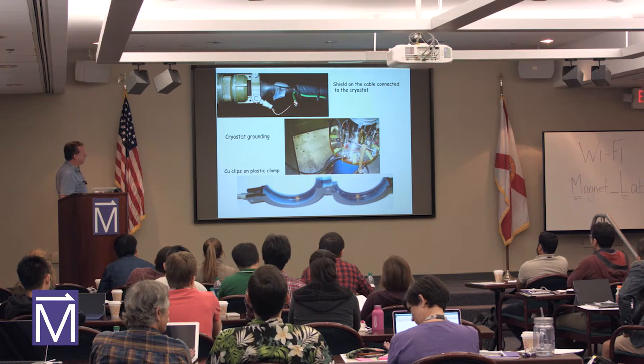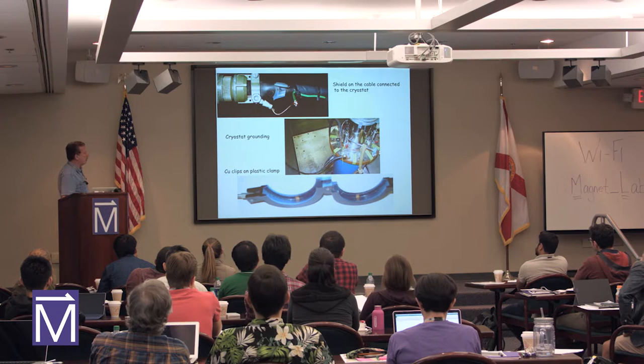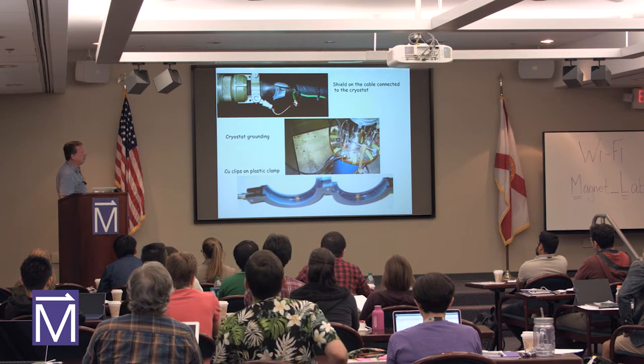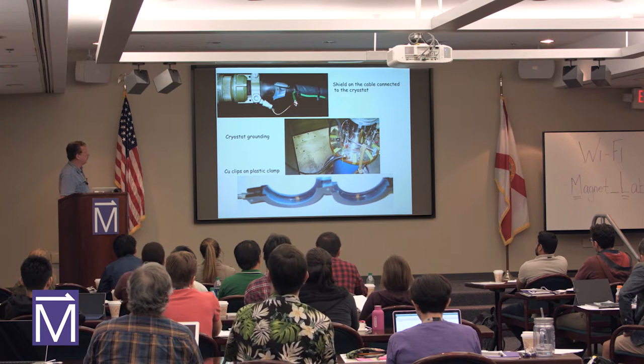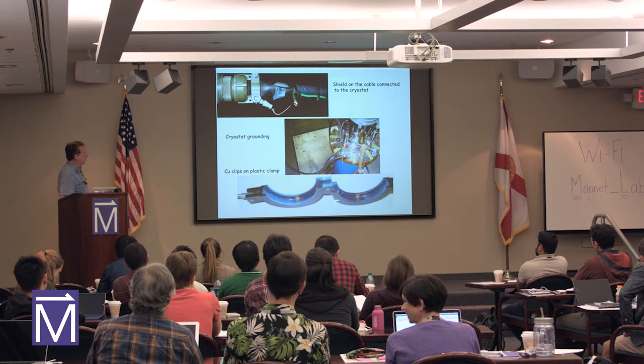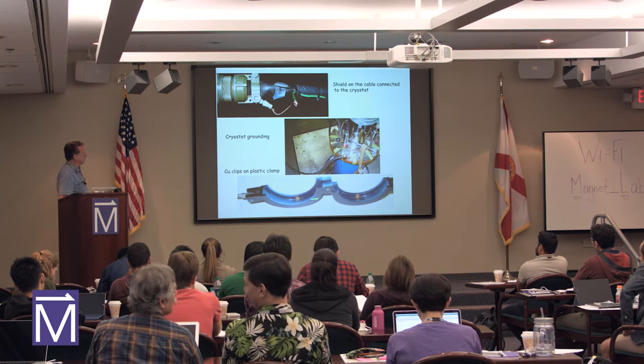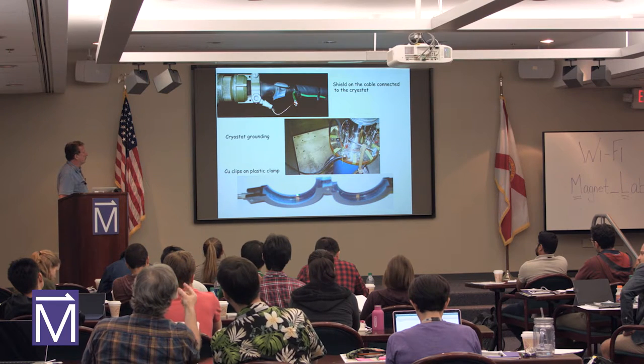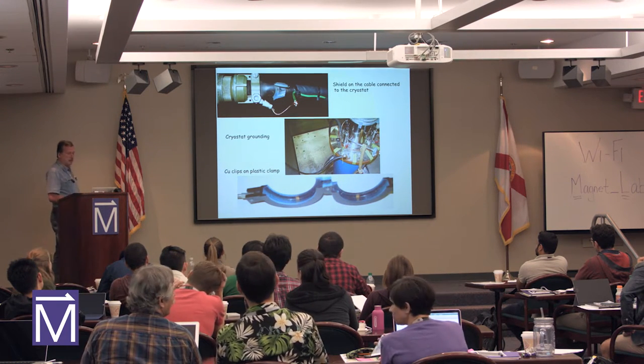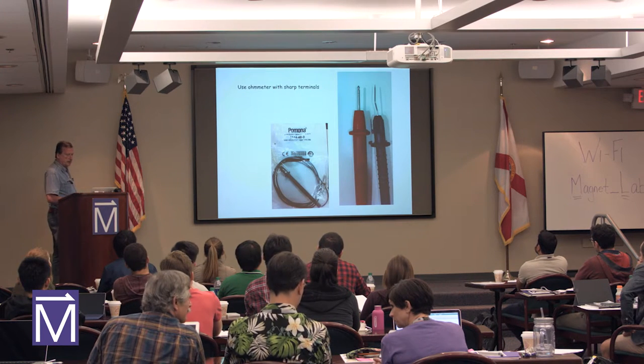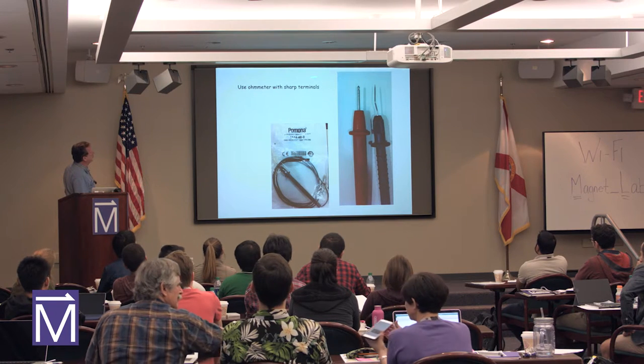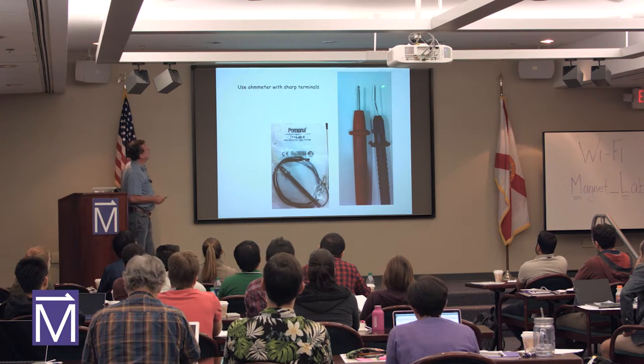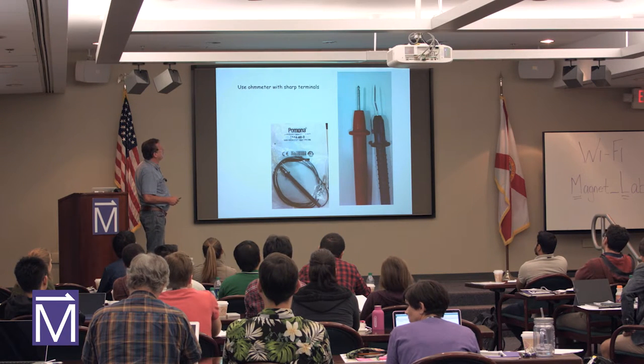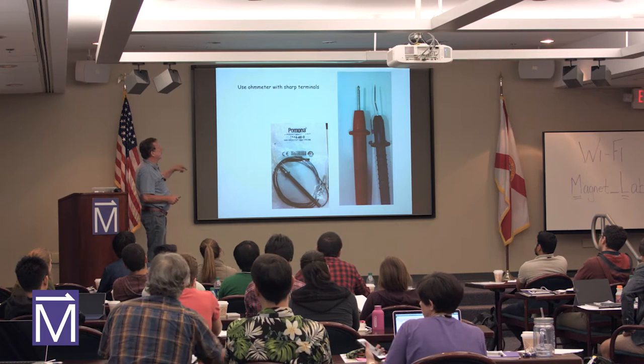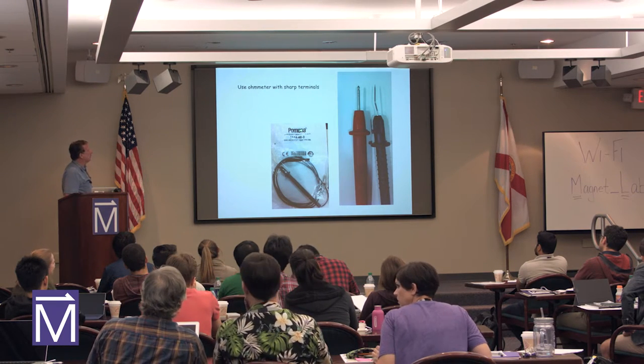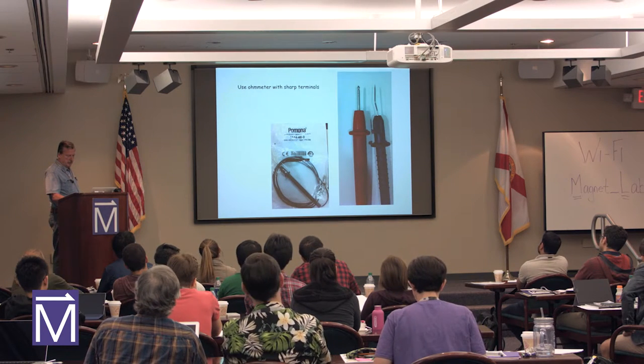Those are typical plastic clamps. You can isolate pumping lines, but remember they are made not to isolate ground, they are made to be cheap. And in industrial application, because of that, they have those small copper or brass clips which must be removed. This is an example of very sharp terminals, which are even sort of dangerous, but you measure with them much more effectively. Also, if you check probes, they fit deep connectors much better. They are produced by Pomona, and I like them very much.